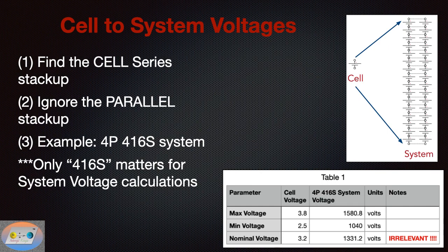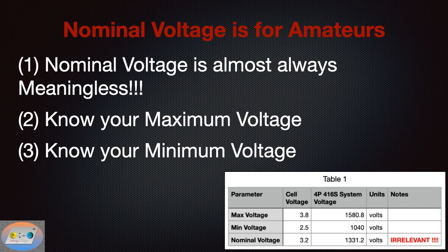Again, always ignore nominal voltage because it is completely useless. However, you might have to list it in your spec sheets for completeness, because some people just expect it. Just to emphasize the point, nominal voltage is for amateurs. There's one esoteric calculation that hardcore battery technical people will use nominal voltage for, but for the most part you don't consider nominal voltage at all. It is almost always meaningless.